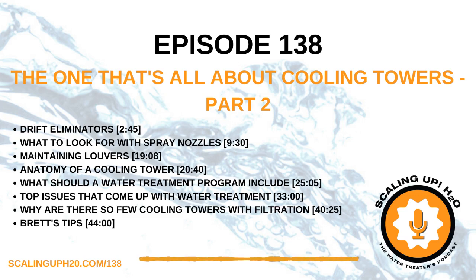People need to realize the point of the cooling tower is to let us concentrate up the solids so we use as little water as possible to properly operate the system. But when we slow the water down, all the solids suspended in the water are going to separate out, and we can start to precipitate concentrated solids, which can create issues elsewhere in the system. So VFDs make a lot of sense on the fan, but you better know what you're doing if you're installing them on your water pump.